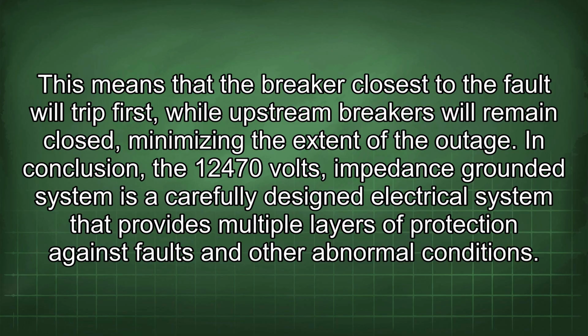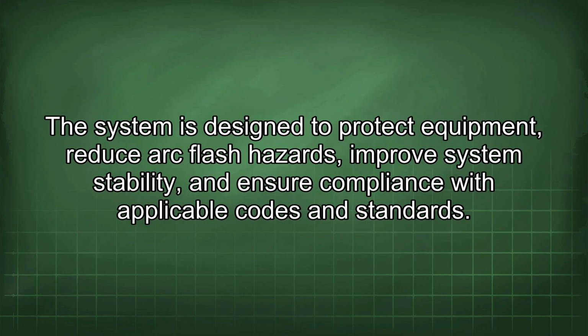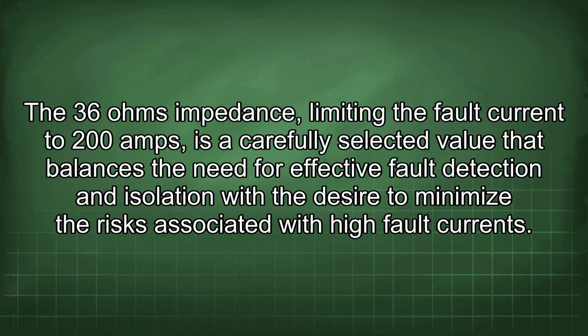In conclusion, the 12,470 volts impedance grounded system is a carefully designed electrical system that provides multiple layers of protection against faults and other abnormal conditions. The system is designed to protect equipment, reduce arc flash hazards, improve system stability, and ensure compliance with applicable codes and standards. The 36 ohms impedance, limiting the fault current to 200 amps, is a carefully selected value that balances the need for effective fault detection and isolation with the desire to minimize the risks associated with high fault current.